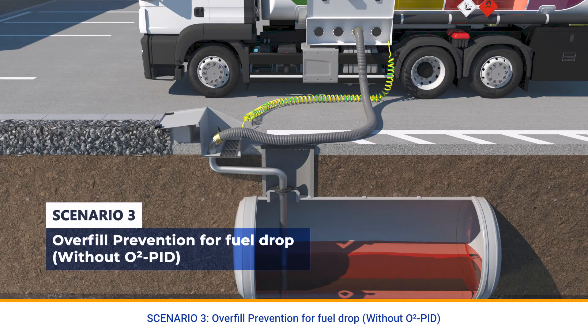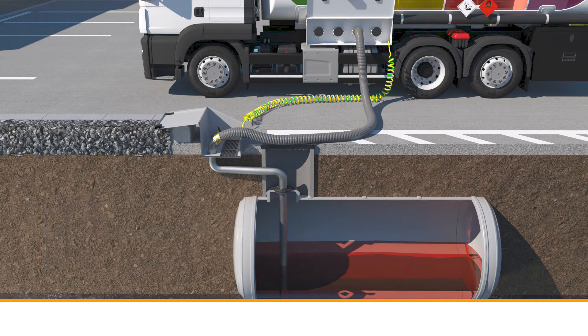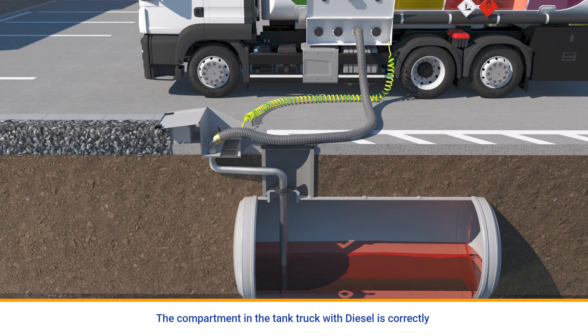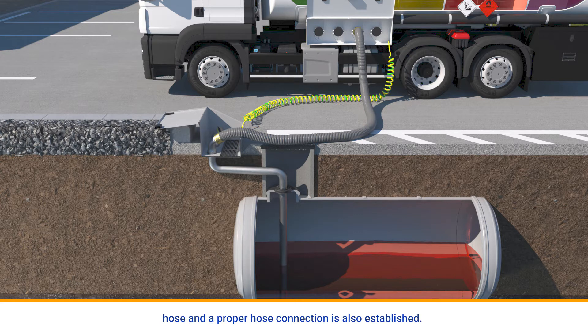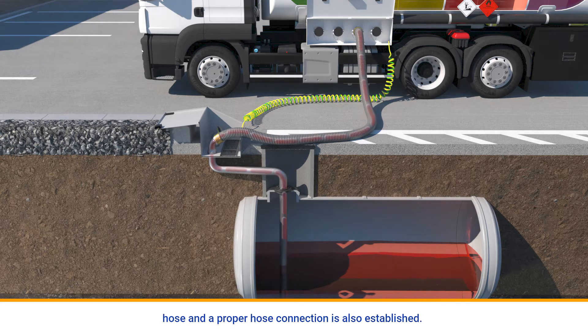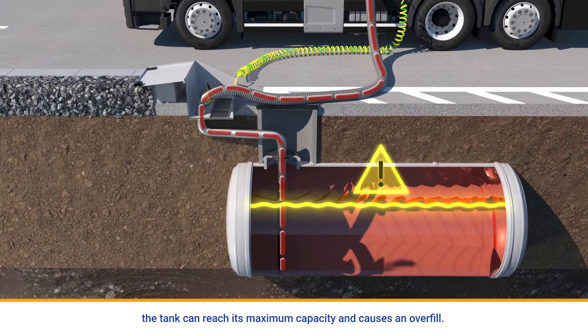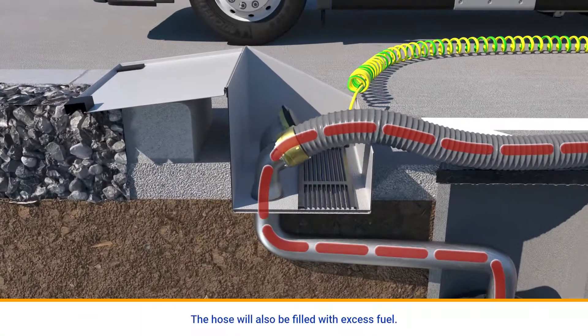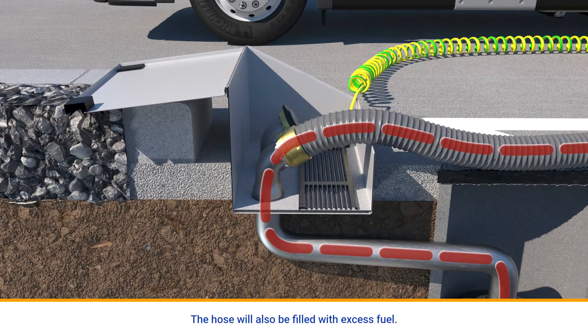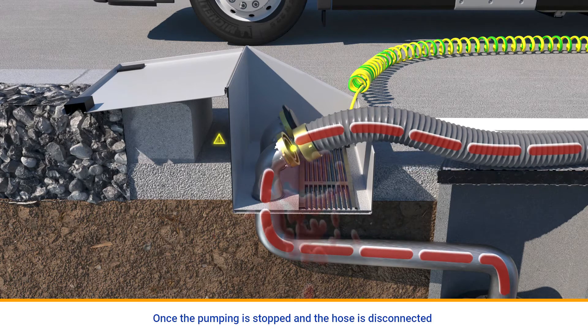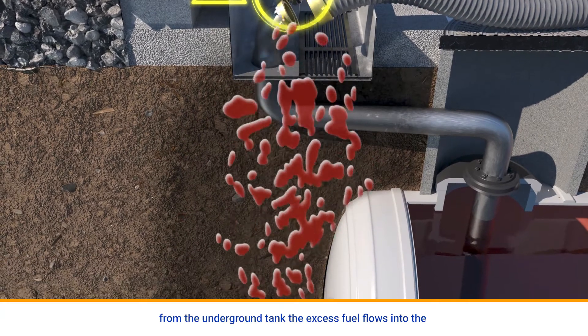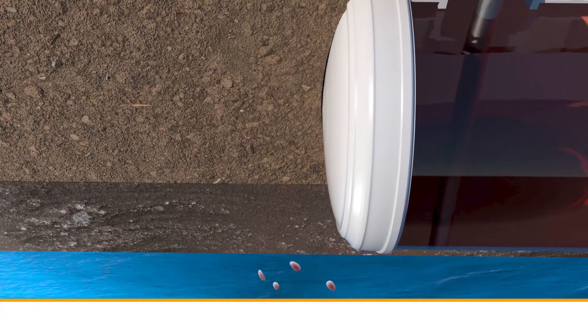Scenario 3: Overfill prevention for fuel drop without O2PID. The compartment in the tank truck with diesel is correctly connected to the diesel underground tank through the filling hose, and a proper hose connection is also established. Without the O2PID, when fuel is pumped into the underground tank, the tank can reach its maximum capacity and causes an overfill. The hose will also be filled with excess fuel. Once the pumping is stopped and the hose is disconnected from the underground tank, the excess fuel flows into the environment and can reach the underground water.